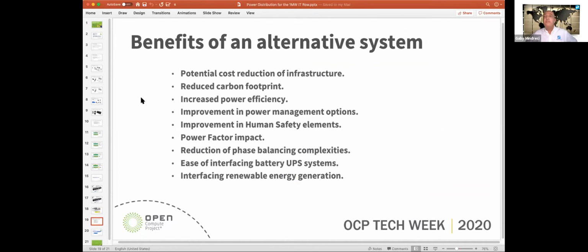Obviously, an alternative system would bring a potential cost reduction of infrastructure. If you think about reduced carbon footprint also, imagine lowering the amount of copper needed to do all this power distribution, because in a data center in three-phase final distribution, we've got miles and miles and miles of cable with a lot of copper in it because it carries a higher current. And just to manufacture those cables, to melt all that copper, to form all that copper, all the insulators and all that, it requires energy, and all that energy turns into the atmosphere in some form. Reducing this infrastructure will reduce significantly the carbon footprint from the startup cost.